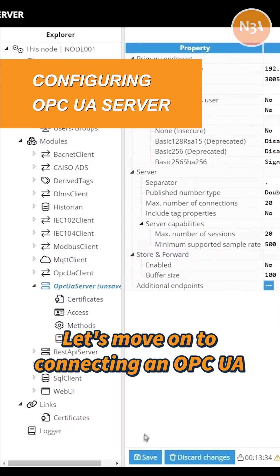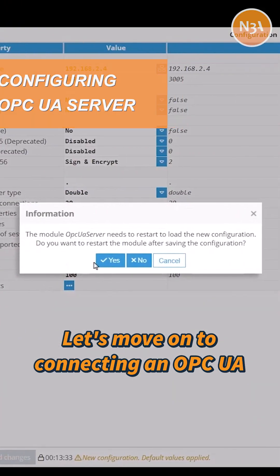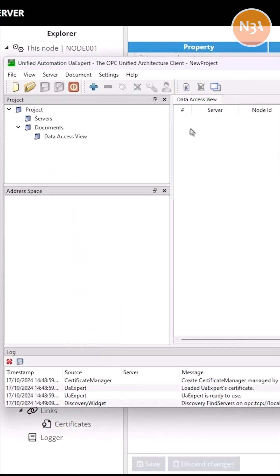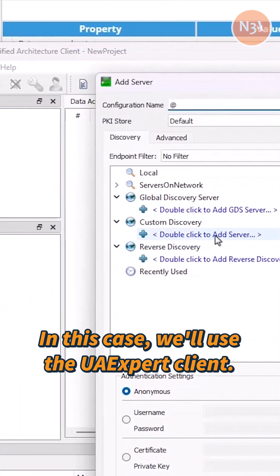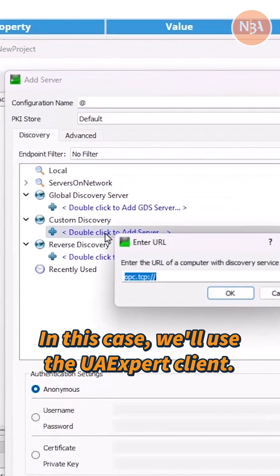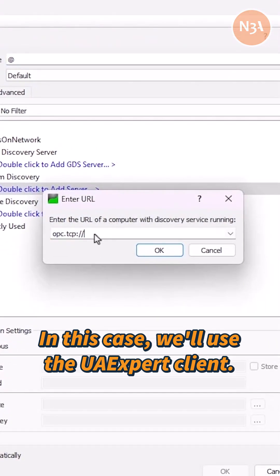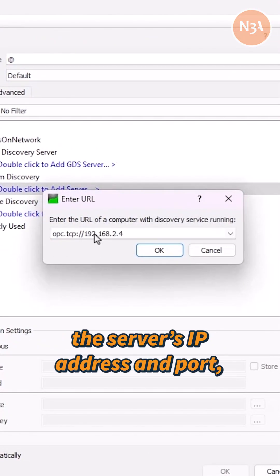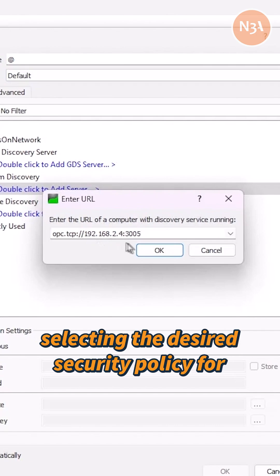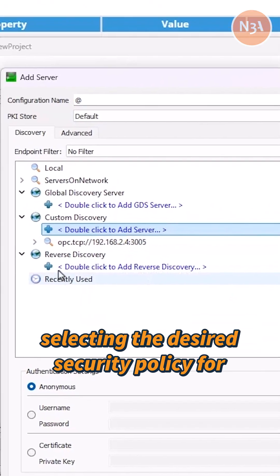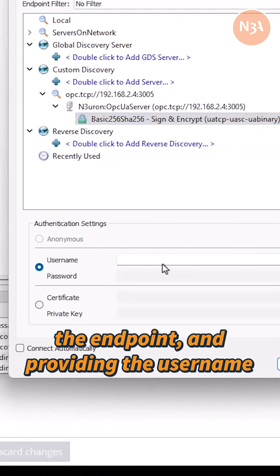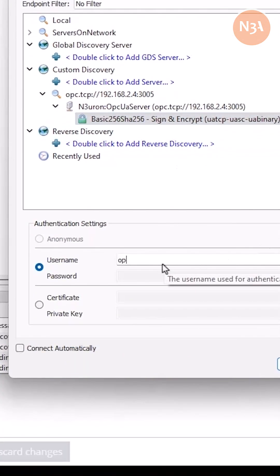Let's move on to connecting an OPC UA client to the server. In this case, we'll use the UA Expert client. I'll configure the connection by entering the server's IP address and port, selecting the desired security policy for the endpoint, and providing the username and password.